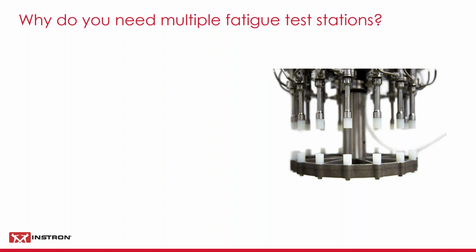Each one of those is stable, and will give you decent accuracy up to the test frequency we need. Depending on the spec, one of those would be a 1 Newton or a 10 Newton load cell, probably 10. And then each one of those fixtures can be individually adjusted. In reality, by the time you've put each one of your little stents into its simulated tube, its simulated artery, it's going to be slightly different length.